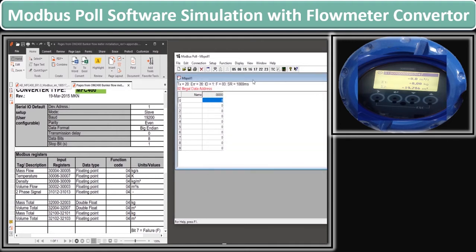You are seeing that an "Illegal Data Address" option is appearing. This means that all the serial parameters are OK and you now have to define the input register, data type, and function code. If the configuration parameters were not OK or communication was not established during wiring, you would get an error of timeout instead of the illegal data address.